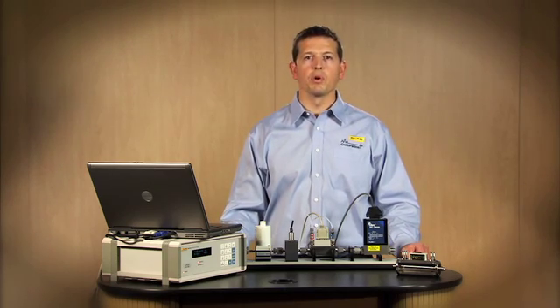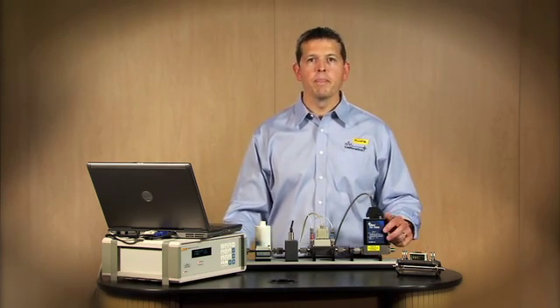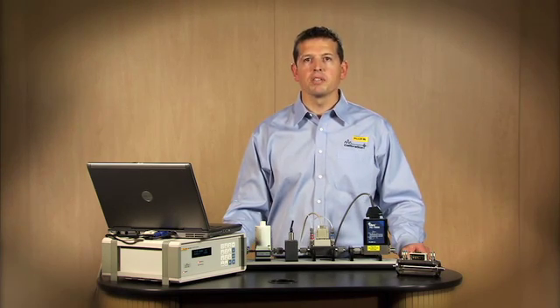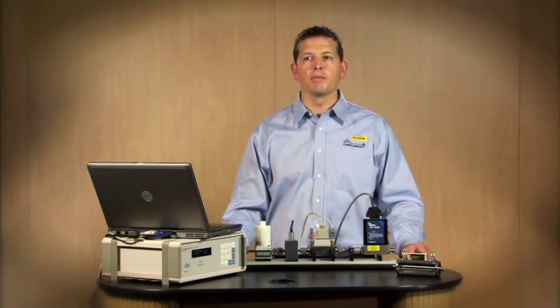The application I want to talk to you about today is for calibration of a mass flow controller or MFC like the one I have here. Mass flow controllers are used for a variety of industrial processes, especially semiconductor and pharmaceutical manufacturing.